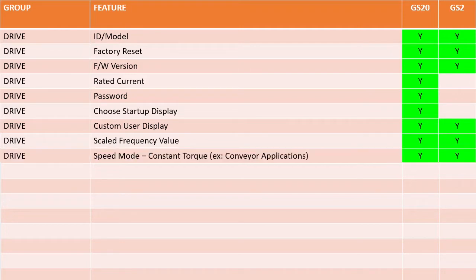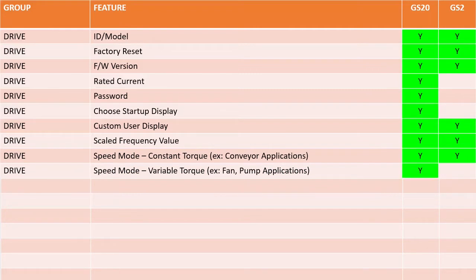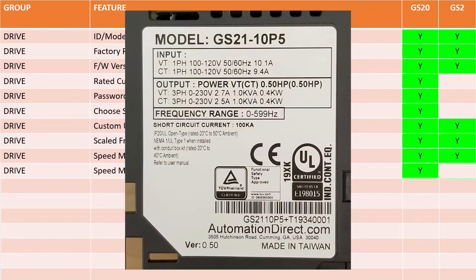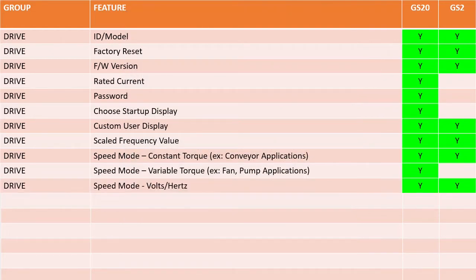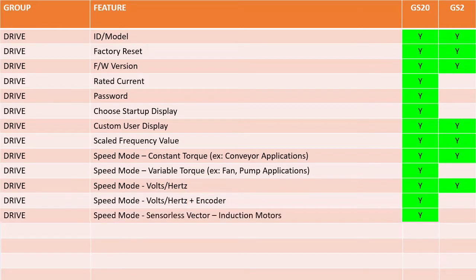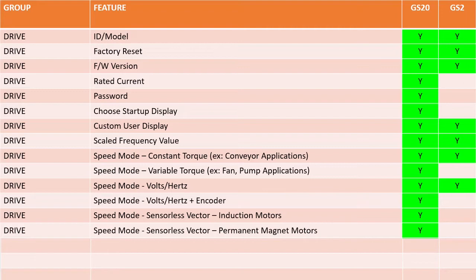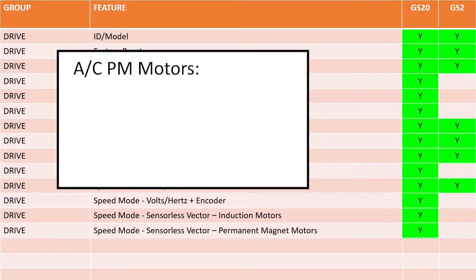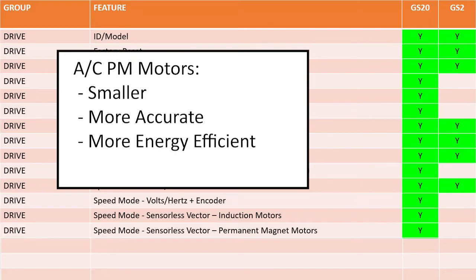The GS20 drive is rated for both constant torque and variable torque applications when in speed mode. The GS2 drive is only rated for constant torque applications like loaded conveyors. Can you use a GS2 drive on a variable torque application like a fan or a pump? Sure, but it falls on you to select the right drive. The GS20 drives tell you right on the label exactly what the ratings are for both constant and variable torque applications and have parameters to automatically optimize the drive for each. In addition to volts-hertz, the GS20 also has volts-hertz with encoder feedback and sensorless vector for induction or permanent magnet AC motors. That's right — the GS20 can do permanent magnet motors, meaning you can take advantage of smaller, more accurate and more energy-efficient AC permanent magnet motors that give you full torque at zero RPM.